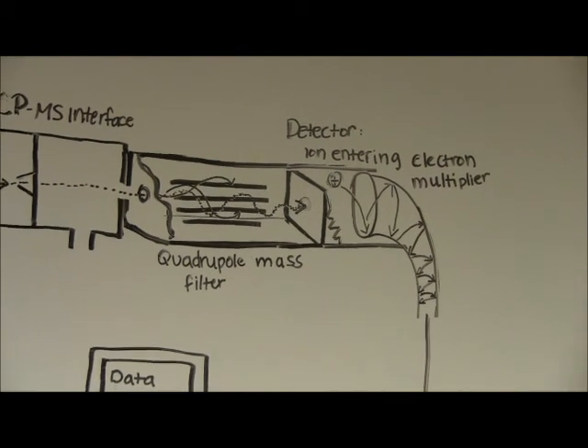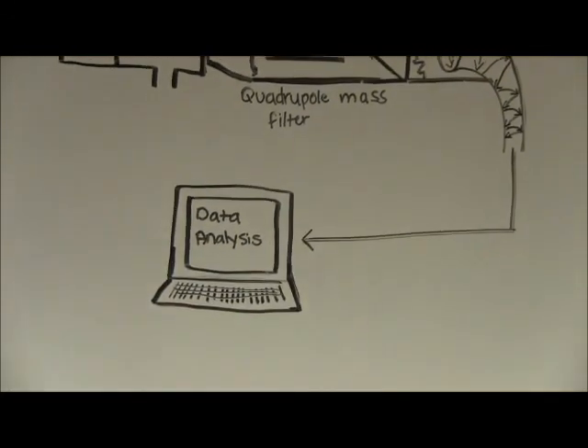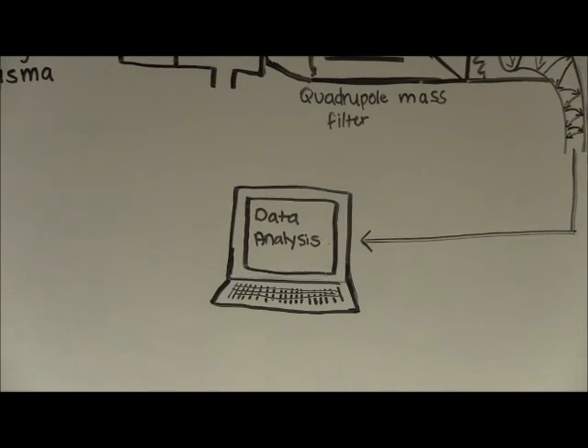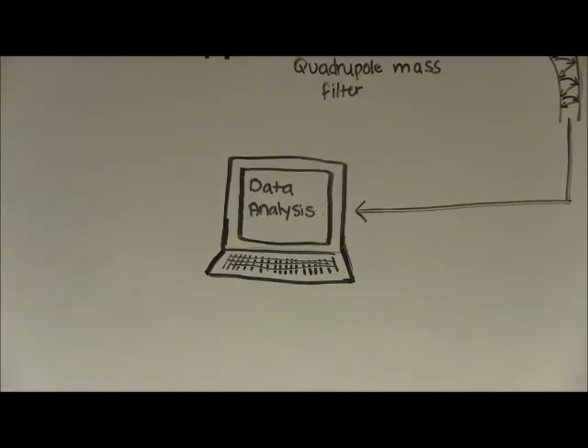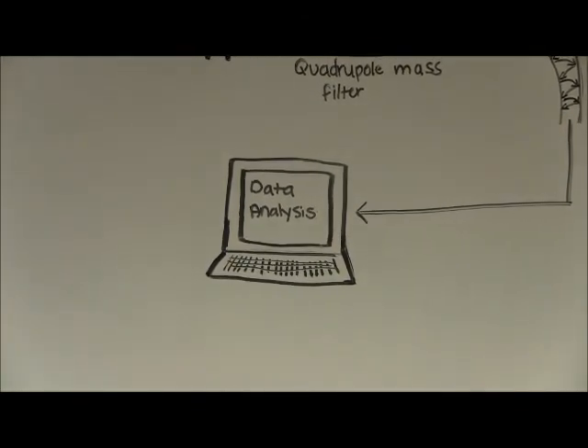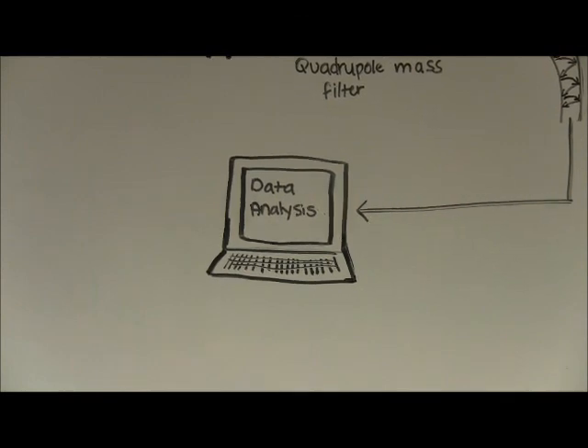One of the great advantages to ICP-MS is extremely low detection limits for a wide variety of elements. Some elements can be measured down to parts per quadrillion range, while most elements can be detected at the parts per trillion levels.